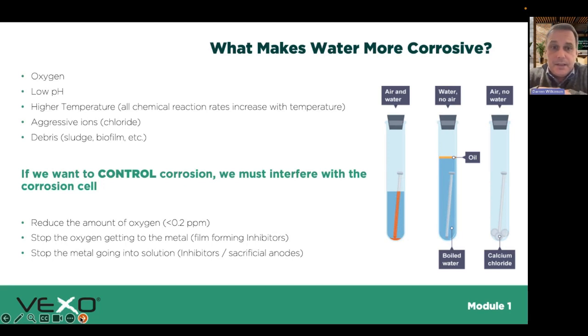And then another corrosive matter we need to consider is debris, sludge, and biofilm. It's like shot blasting inside of the pipework. So if you are using corrosion inhibitor, it'll struggle basically to lay down its film. So you've got to maintain a good level of clean water at the same time, free of suspended solids. So if we want to control corrosion, we need to basically interfere with the oxygen.